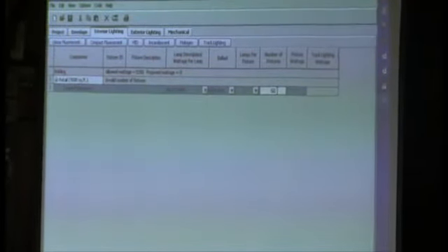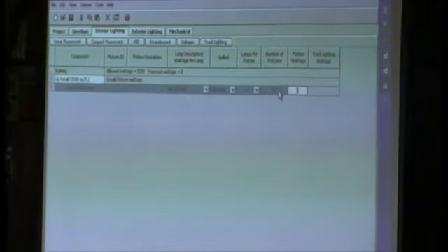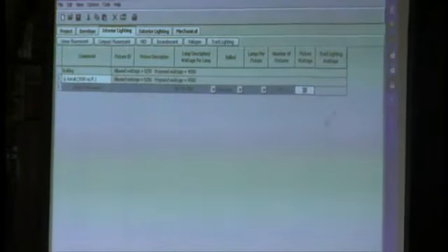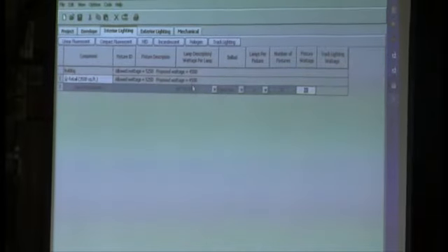So you put in your lighting schedule. I've got some 4-foot T8 32 watts. They have an electronic ballast. They have 3 lamps per fixture, and I've got 50 of those in my building. Each one of those fixtures is 90 watts. And I crunched it out, and it said, okay, you just burned up 4,500 out of the 5,250 of your design.